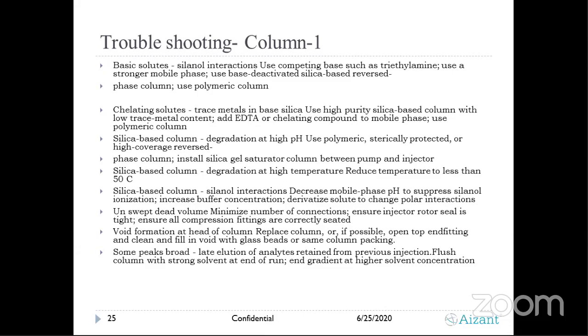On the pH part, I think I had discussed just now. Now coming to the dead volume, I will discuss this point again in the upcoming slide: how the impact of dead volume comes into the picture on the peak shapes with respect to the column. And you will find there is a void formation at the head of the column. Again, we can discuss that in the upcoming slide. There are 2 slides for this particularly. And I think we have discussed the late eluting previous injections, how they can contaminate the upcoming runs. So I always recommend that for the wash method we are using for any HPLC, how it has to be done, what the polarity of the wash solvent should be, and when we are changing from one methodology to another, what precautions we have to take. I think that has been discussed in the previous slides. If there are any specific questions, we can discuss them at the end of this presentation.